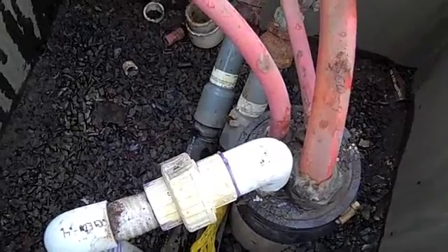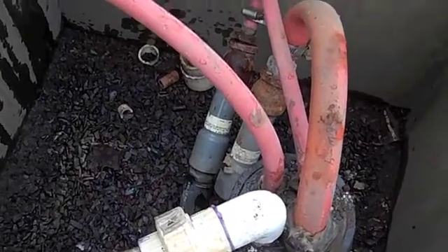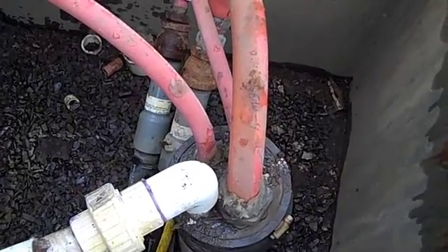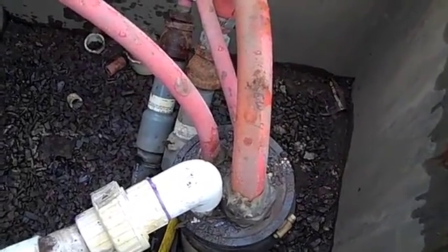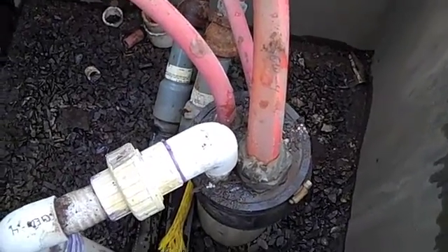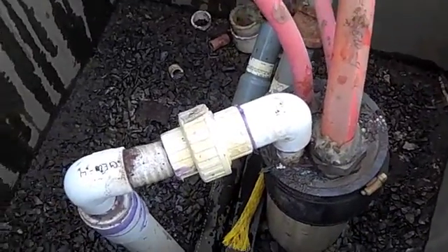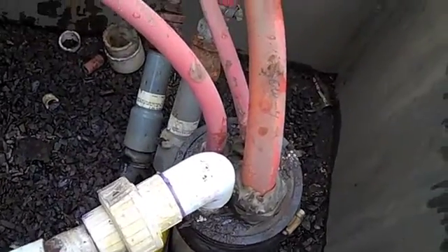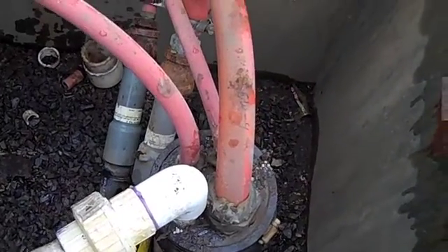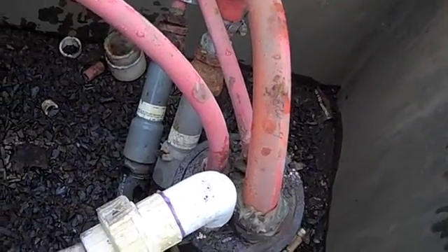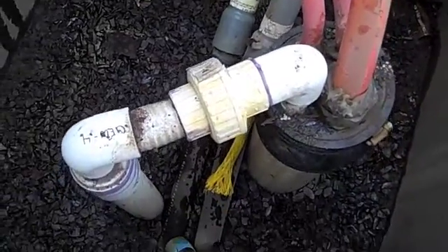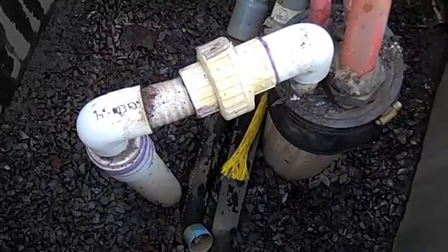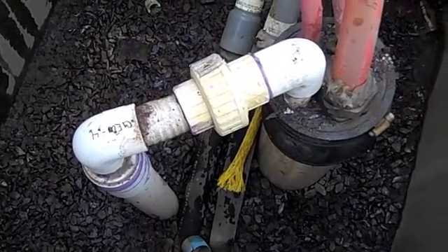So compressed air is delivered from the shed through underground trenching, through that 3/8-inch air line, down to the pneumatic pump. The pneumatic pump powers the groundwater extraction, exiting the well through the white PVC line, in addition to the soil vapor extraction provided by the rotary claw vacuum pumps coming out the 1-inch air hose, and both the groundwater extraction and soil vapor extraction are transported back to the shed for treatment.